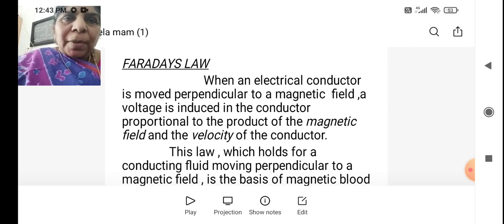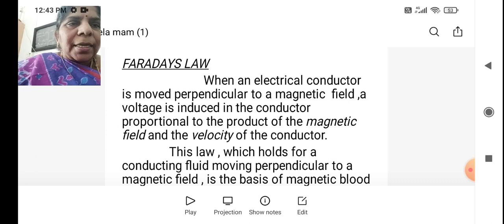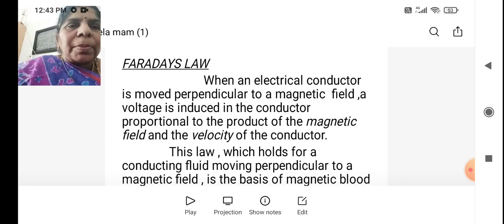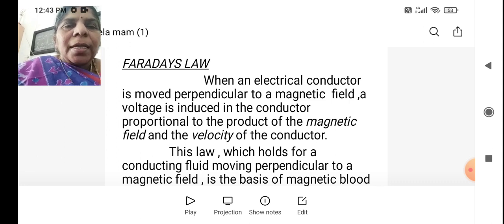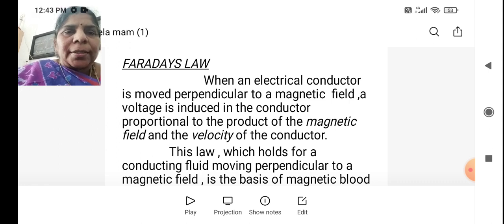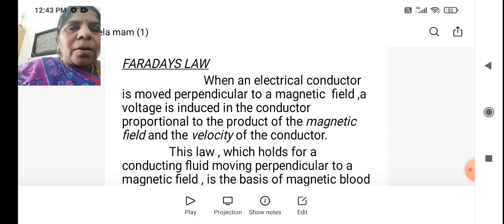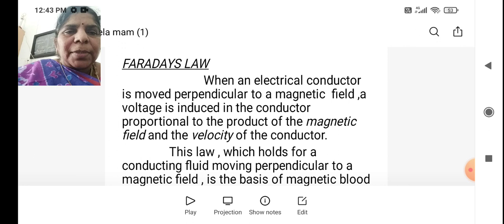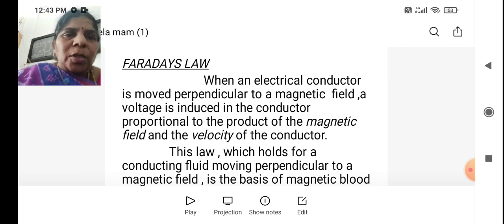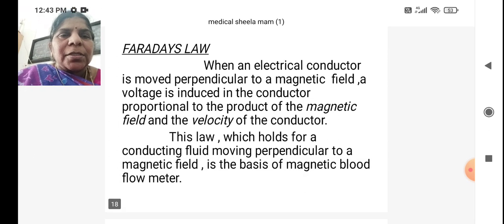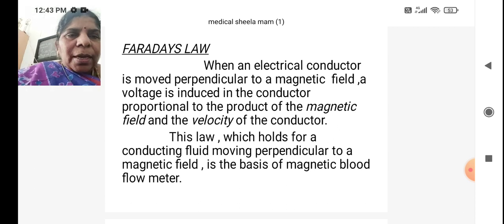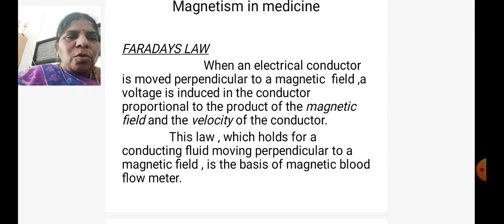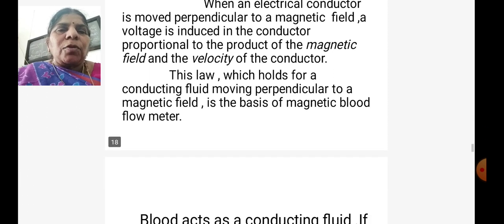We all know what Faraday's Law is. When an electrical conductor is moved perpendicular to a magnetic field, a voltage is induced in the conductor, which is proportional to the product of the magnetic field and the velocity of the conductor. This law, which you have applied in electromagnetism, can be applied to a conducting fluid moving perpendicular to a magnetic field, which is the basis for magnetic blood flow meter.